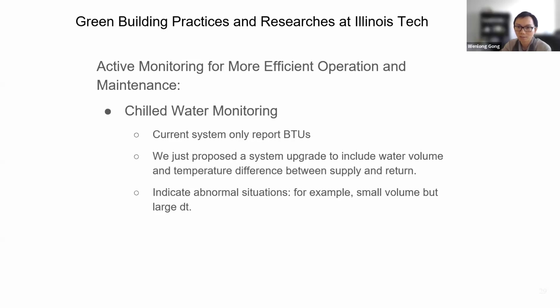With those added, for example, if you see a small volume of water but a large delta T, you might want to send a maintenance person to check the pipe insulation or heat exchangers, something like that.